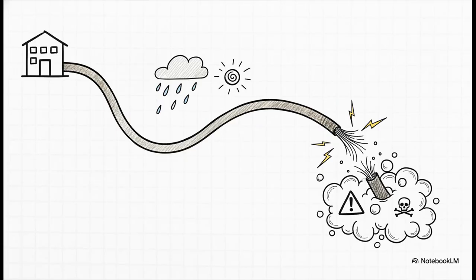You can pick the absolute perfect Ex d flame-proof motor, or carefully select a highly rated Ex i barrier and still create a massive hazard if the cable feeding it or the gland sealing it just isn't built for the job. The best equipment absolutely fails with the wrong cable.